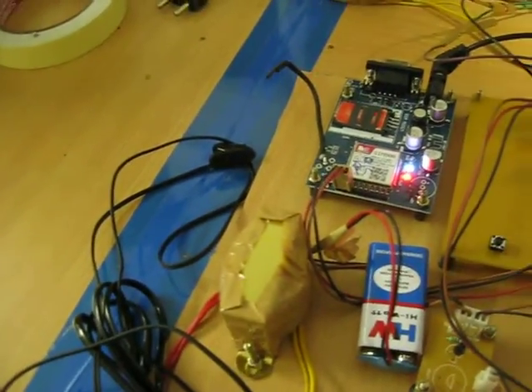Now, please send an SMS to the number stored. Now we got the SMS alert: high heart rate, with the heart rate given. Like this we will get the SMS alerts. Also, according to the alert, we can send pulse 1 and pulse 2. When we send pulse 1 and pulse 2 by SMS, the defibrillator will give a shock to the patient.